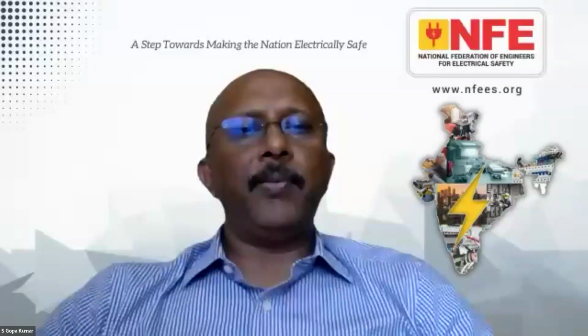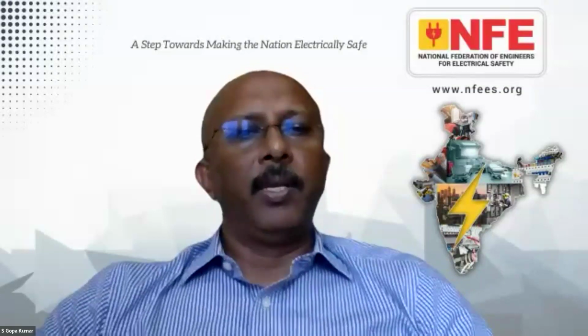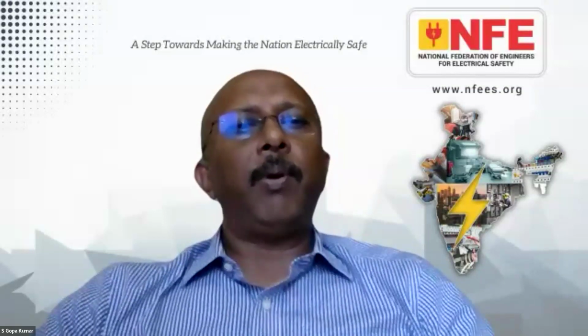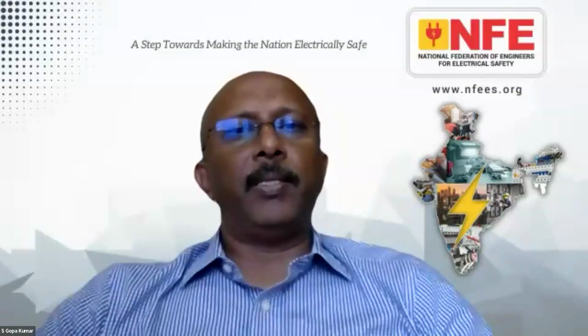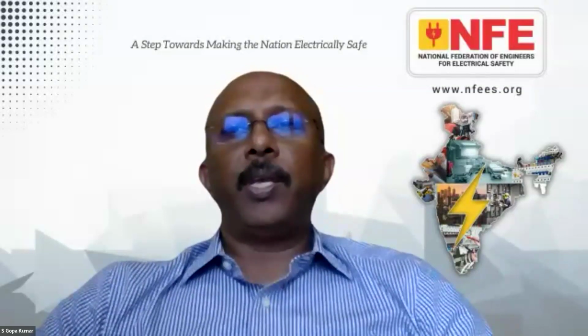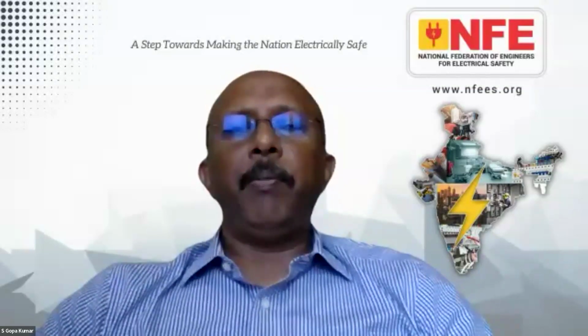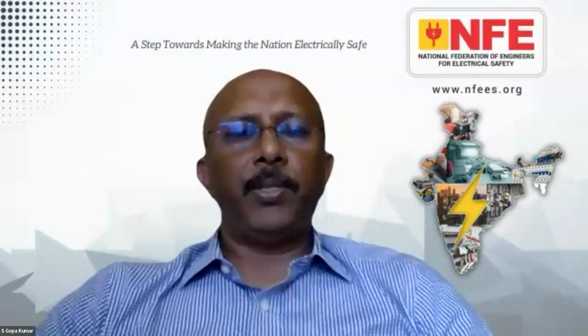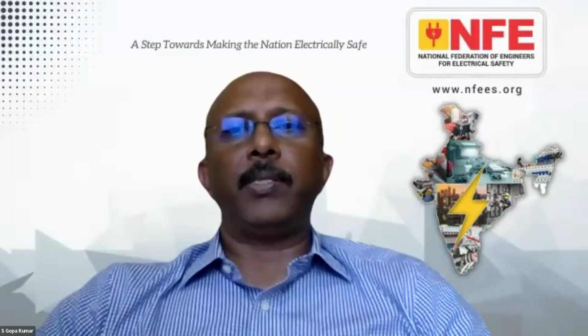Yes. So basically, this device is not creating any voltage. It is only using the voltage available on the supply to make the test. Anyway, the minimum basic required safety measures are already there in the guideline of the device.